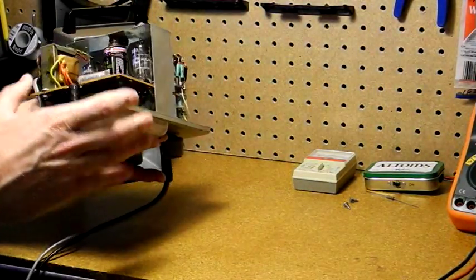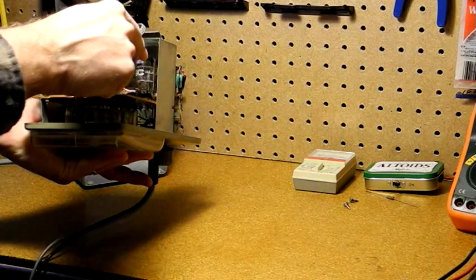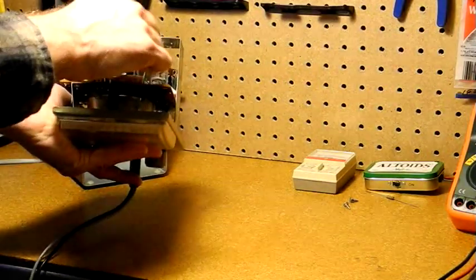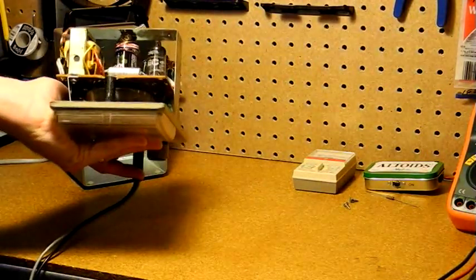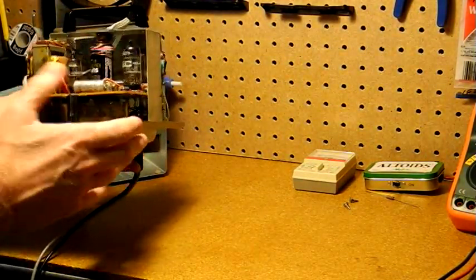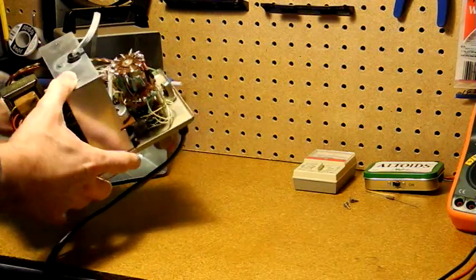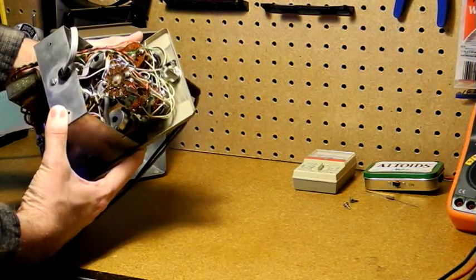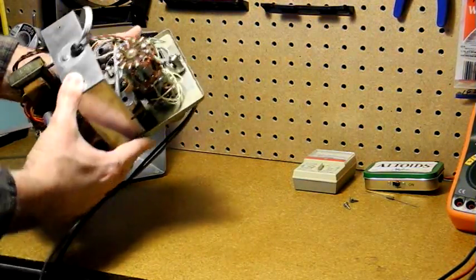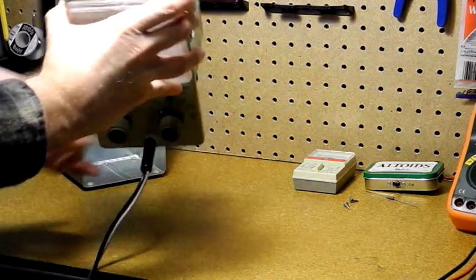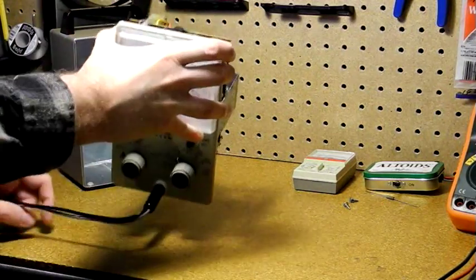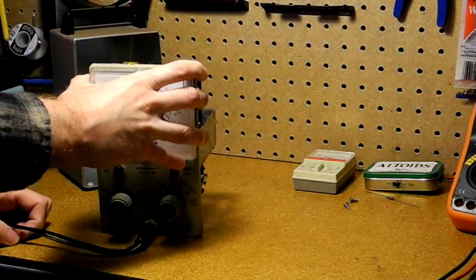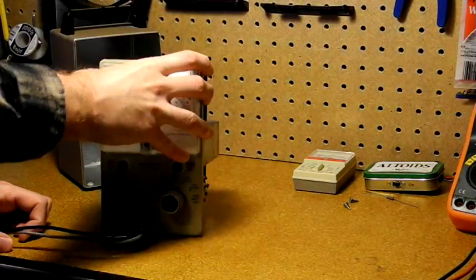Power transformer, two vacuum tubes, and the C battery that's used for the ohms function. There's one adjustment inside that could be used for calibrating it. In fact it can be calibrated by using a built-in voltage reference. It doesn't require any external test equipment.